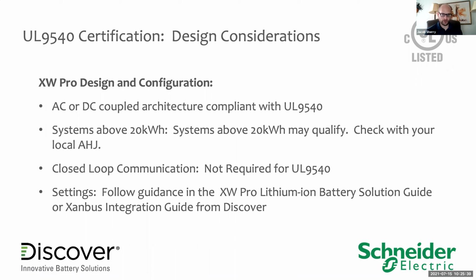Again, as we mentioned earlier, the UL9540 standard applies to systems up to 20 kilowatt hours. Systems above that, you just want to check with your local AHJ. There is no requirement for closed loop communication in order to achieve compliance with UL9540. So it can be used with just regular open loop, manual programmed settings.